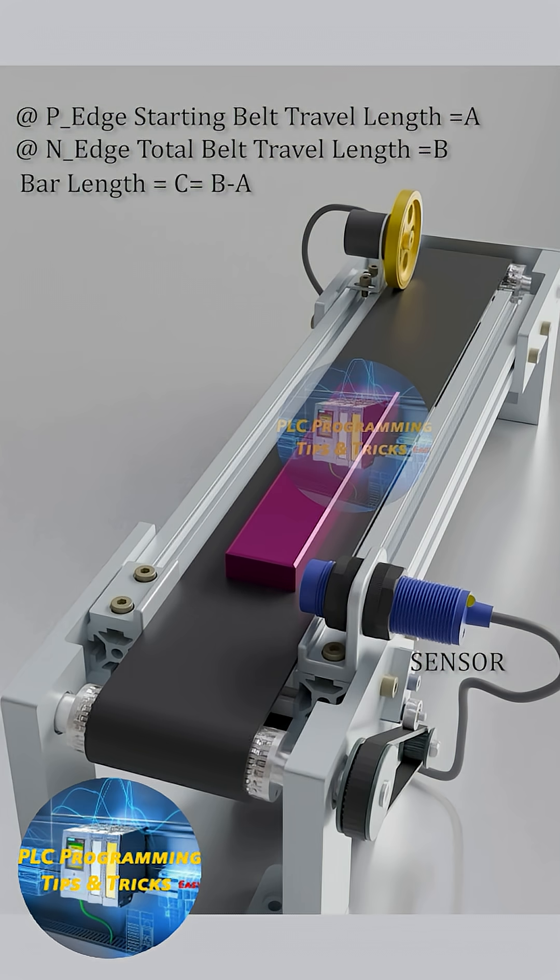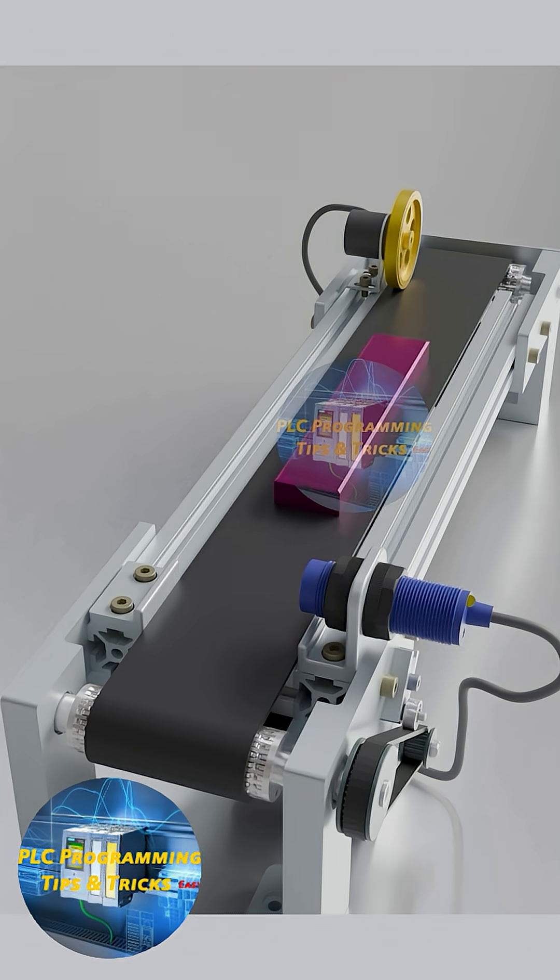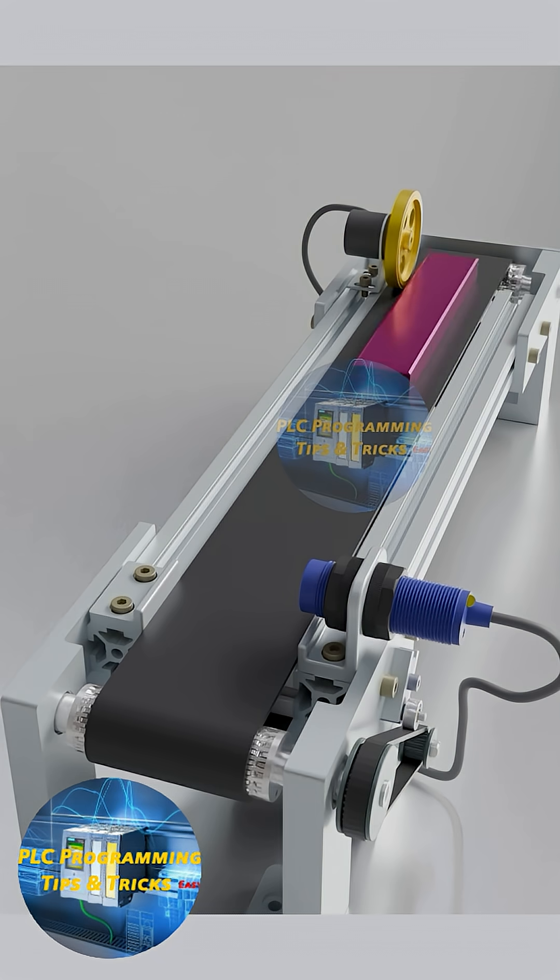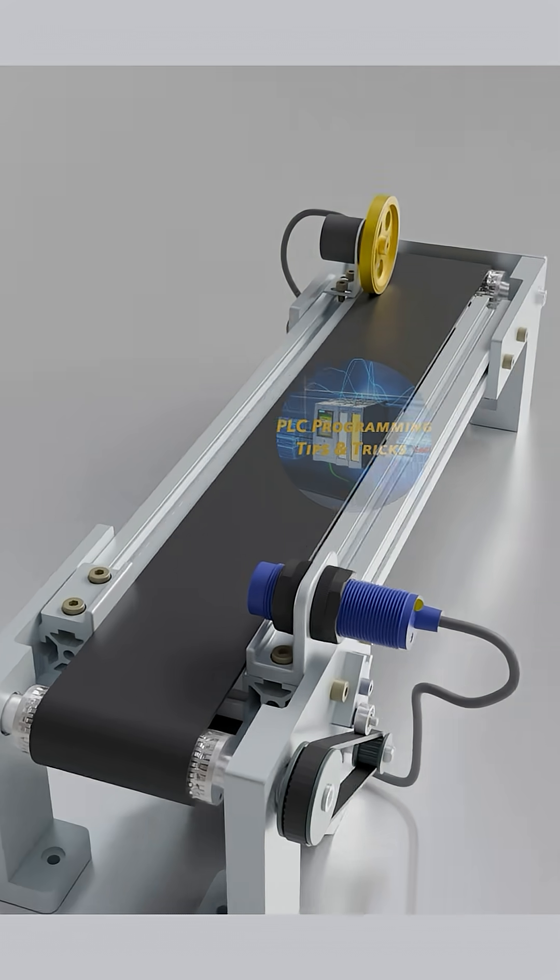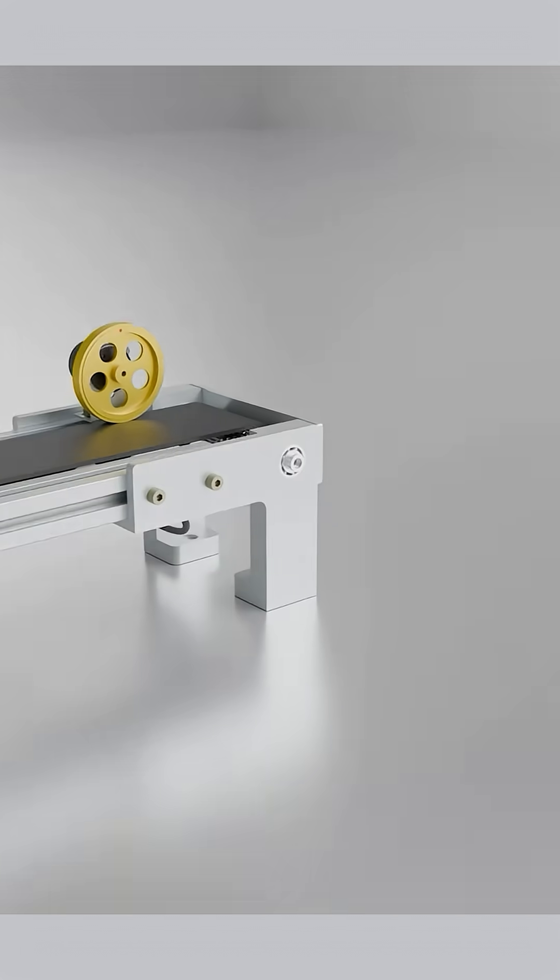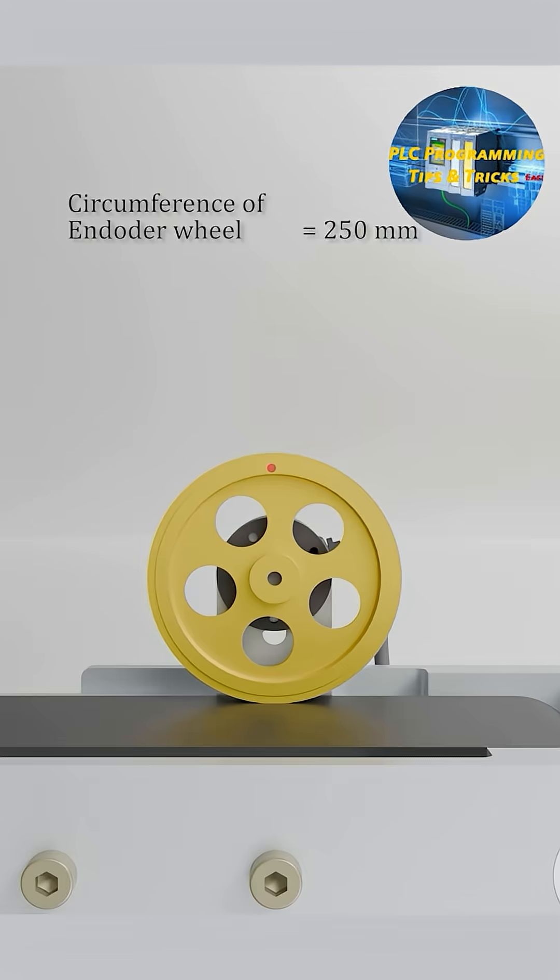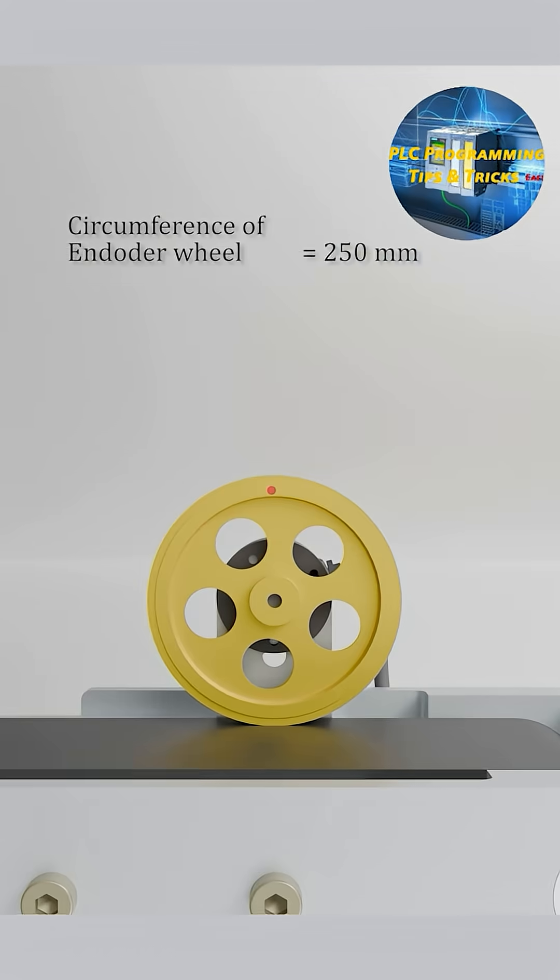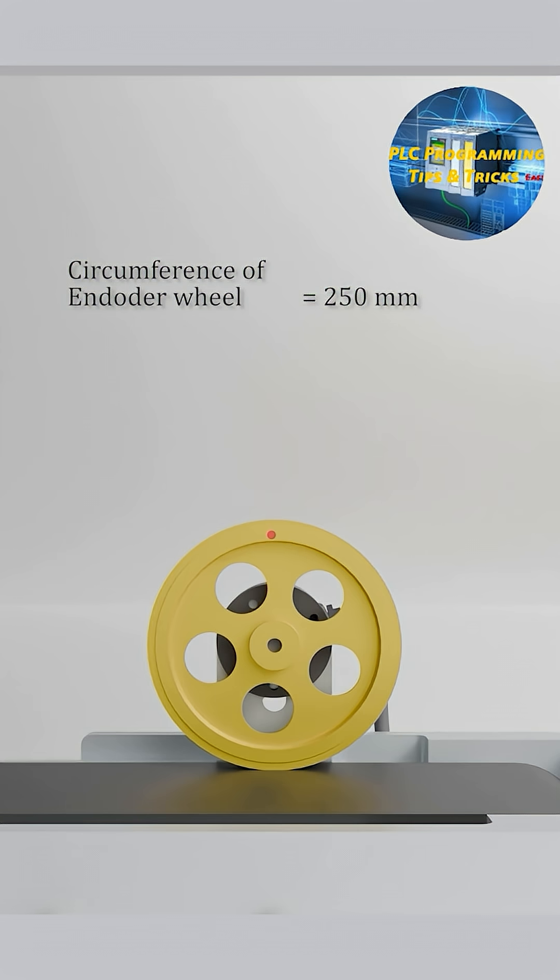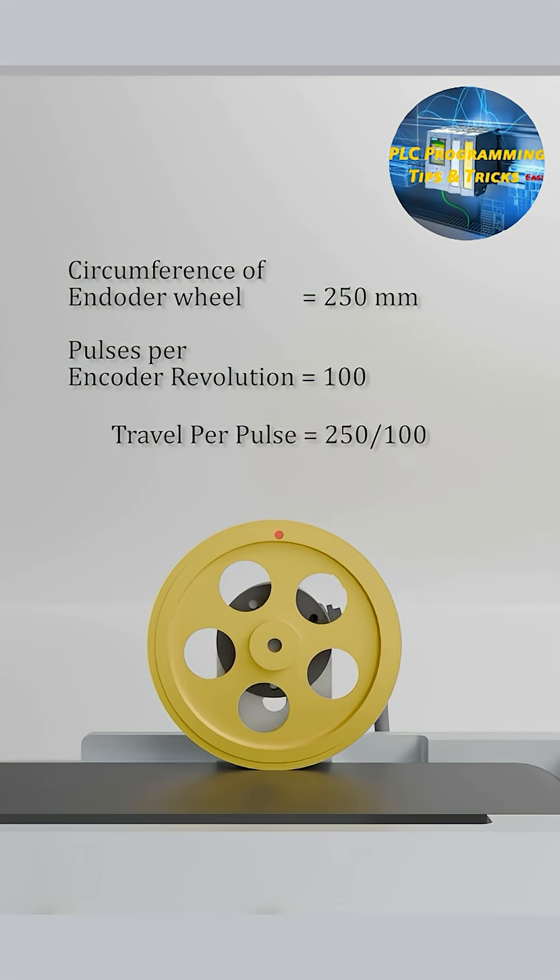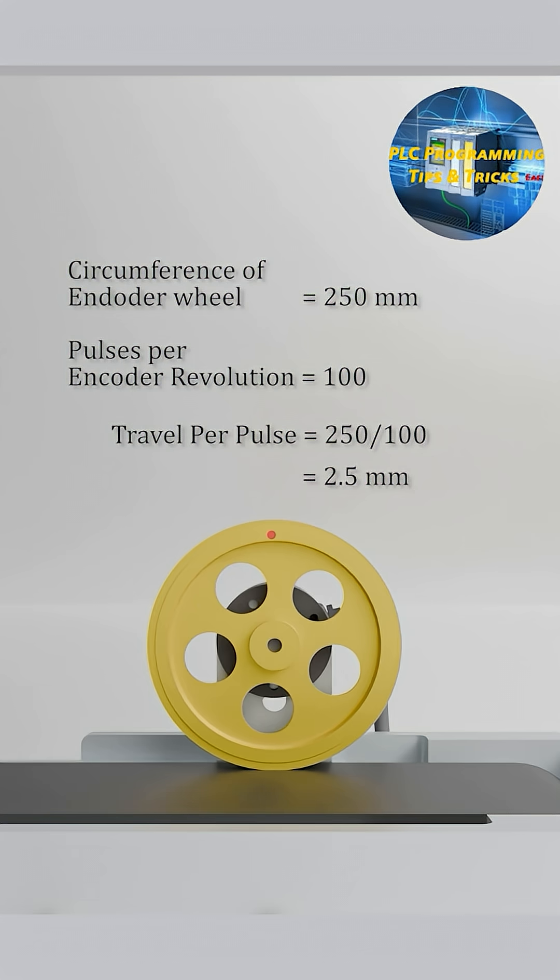Now, the question is how we can detect or measure the distance travelled by the belt. Know the circumference of the encoder wheel. In our case, the circumference of the encoder wheel is 250 mm. Next, the encoder pulses per revolution is 100. So the distance travelled by the belt per pulse of the encoder will be equal to 250 divided by 100, and it is 2.5 mm.